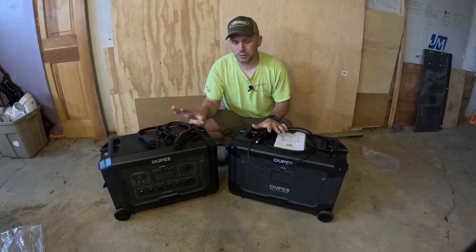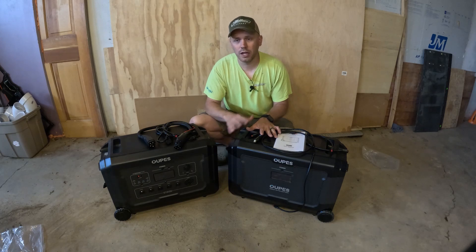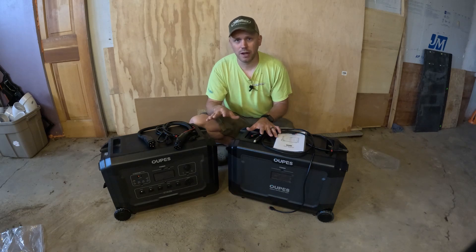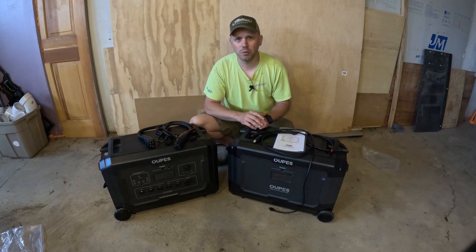The first thing we're going to do is get everything hooked up, connect the two units together, run a load on it, and drain it down completely. Per OUPES's instructions, they want you to drain the batteries completely dead and then charge them up fully. This will help program the BMS and get everything working the way it needs to.